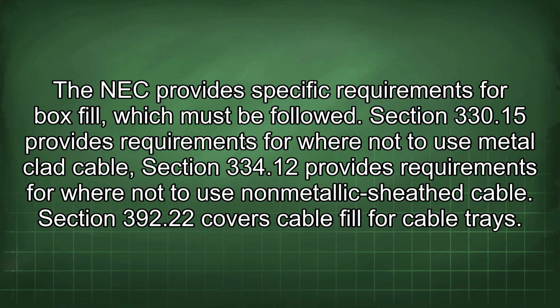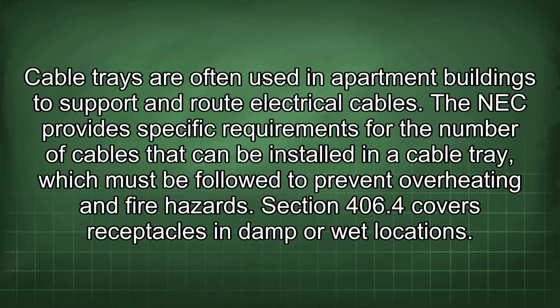Section 392.22 covers cable fill for cable trays. Cable trays are often used in apartment buildings to support and route electrical cables. The NEC provides specific requirements for the number of cables that can be installed in a cable tray, which must be followed to prevent overheating and fire hazards.